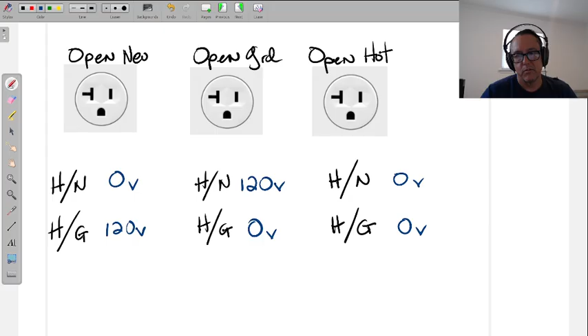Most common problem, if something is not working, is either no hot or no neutral. Open ground, yes, this is important. Absolutely. And by the way, I put negative here. I don't want to do that. So it's just the reverse when we have an open ground. We're going to have 120 between the hot and the neutral, and then we're going to have nothing between the hot and the ground. And then open hot, you're going to check between the hot and the neutral, 0 volts. Wait a minute, is it no hot or is it no neutral? Now we'll check between the hot and the ground, and then we'll have 0 again. That's just telling me that hot is not available with either the neutral or the ground.